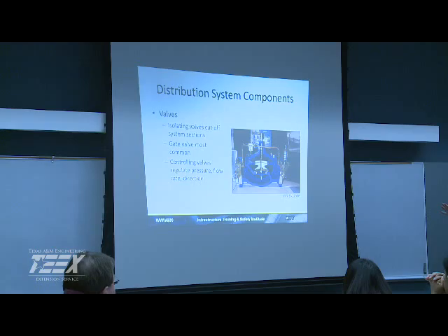It's all the same type of valve, different name. Used for the same thing, works off of differential pressures, and it's going to either open or close depending. Especially on big high service pumps, you're pushing out a lot of water, you want to keep back pressure on your pump, so you're going to have a pressure sustaining valve put off your high service pump to be able to keep that back pressure, keep it in the pump curve properly. And then just some of the examples, going to diaphragms and all.